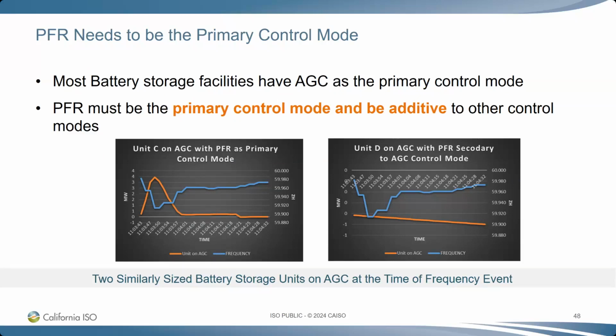The one on the left is the good example, the one on the right is not. The left provided frequency response - they made sure they had their primary control mode set, and they were able to respond more quickly. The one on the right was not set that way - they had their PFR on secondary AGC control mode, and were not able to respond the way they should have. When we talk about it being additive...